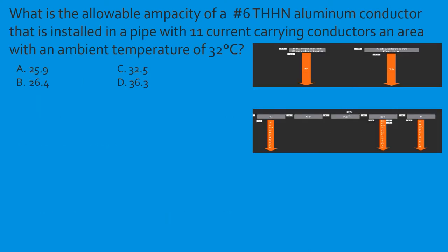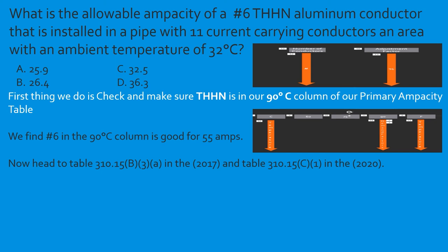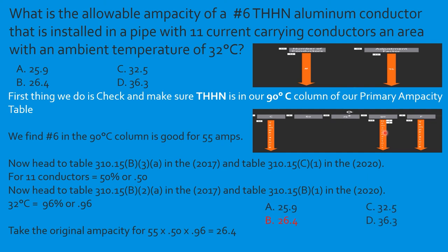Question: What is the allowable ampacity of a number 6 THHN aluminum conductor installed in a pipe with 11 current-carrying conductors in an area with an ambient temperature of 32°C? Confirm insulation is in the 90°C column. Number 6 aluminum is 55 amps. Eleven conductors — bundling adjustment factor is 0.50. Temperature at 32°C — start on the Celsius side, come all the way over to the 90°C column — correction factor is 0.96. So: 55 × 0.50 × 0.96 = 26.4 amps. Select B.